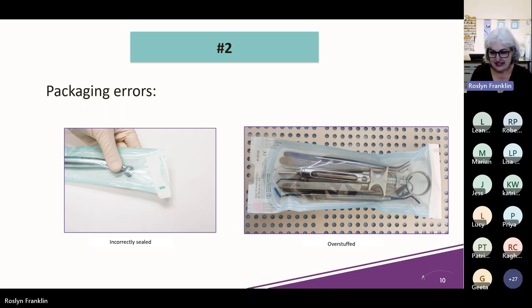Mistake number two: improper packaging of your RMDs is another common mistake I've seen. I'm talking about sterilization bags or plastic paper pouches. These are designed with plastic on one side and special paper on the other, and it's the paper that allows the steam to come through to the instruments, transferring heat that kills the bugs on there.